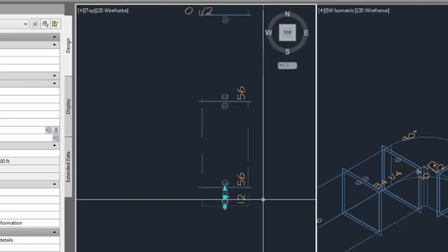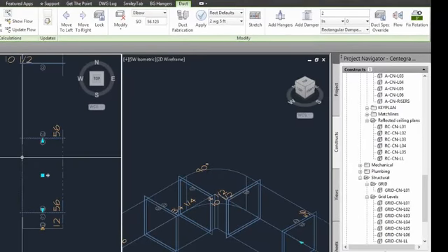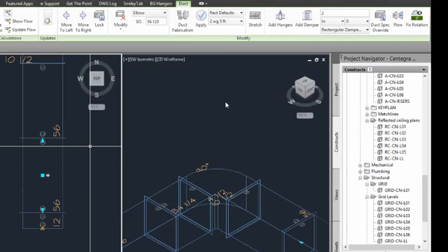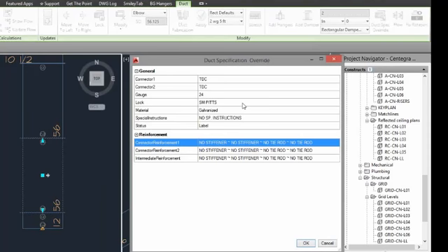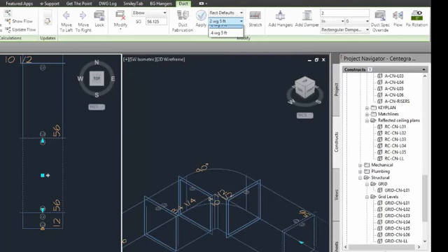If you need to change this from a 2-inch to a 4-inch pressure class, you should never really come in here to your duct spec override and say, okay, I want my gauge now to be 22, I want this to be a large pitts. Don't change your entire pressure class by using the duct spec override. Instead, use the tools provided to change it this way. It makes for a lot cleaner download to Duct Maker when you go to download.